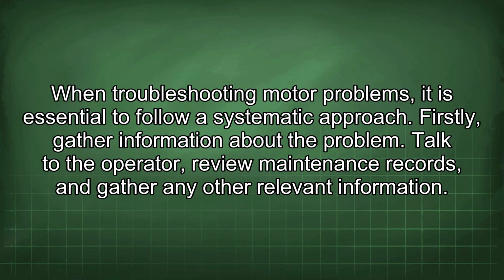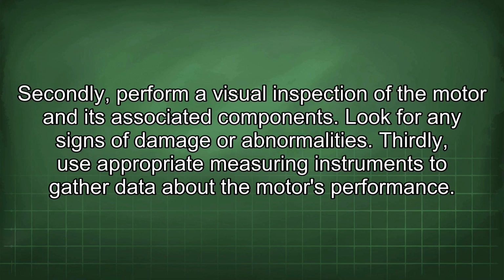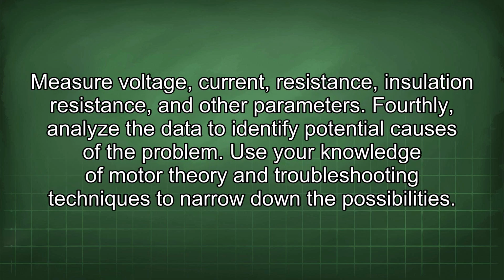When troubleshooting motor problems, it is essential to follow a systematic approach. Firstly, gather information about the problem. Talk to the operator, review maintenance records, and gather any other relevant information. Secondly, perform a visual inspection of the motor and its associated components. Look for any signs of damage or abnormalities. Thirdly, use appropriate measuring instruments to gather data about the motor's performance. Measure voltage, current, resistance, insulation resistance, and other parameters.